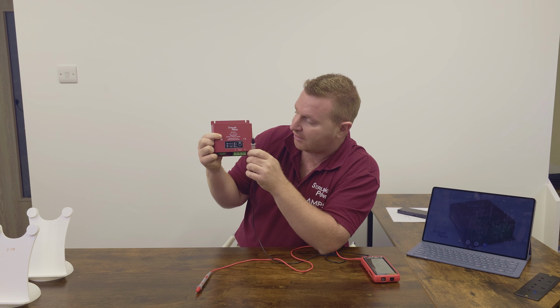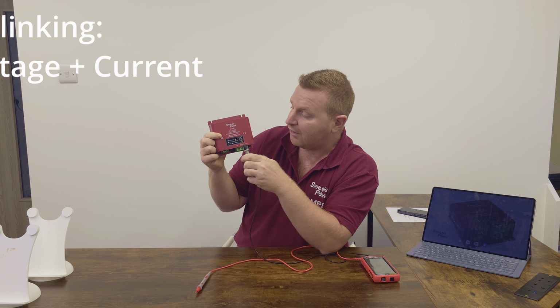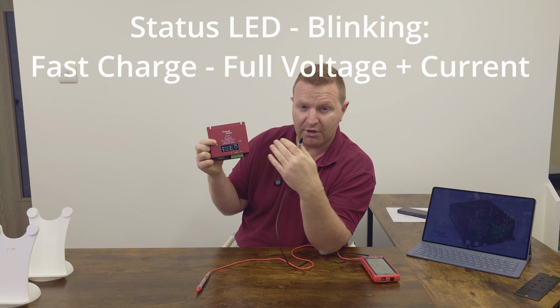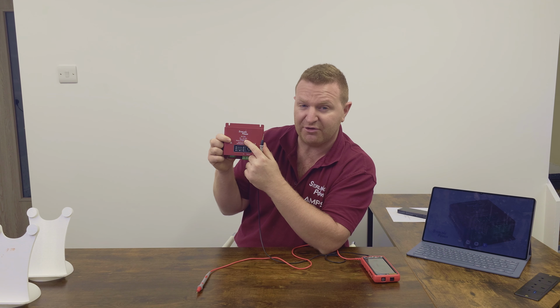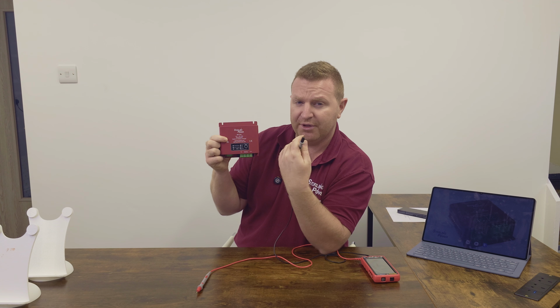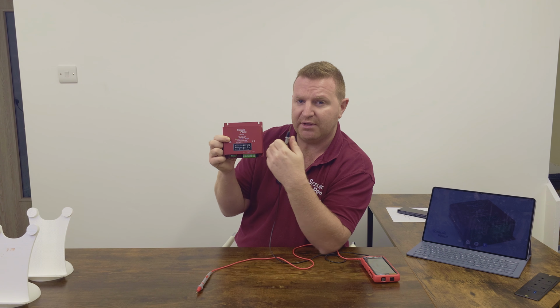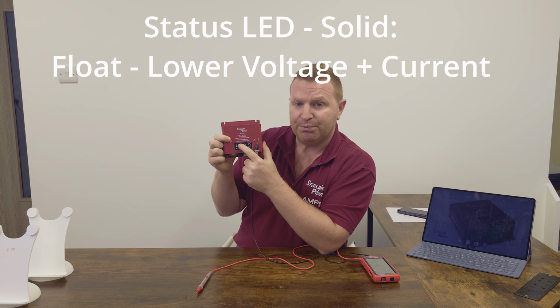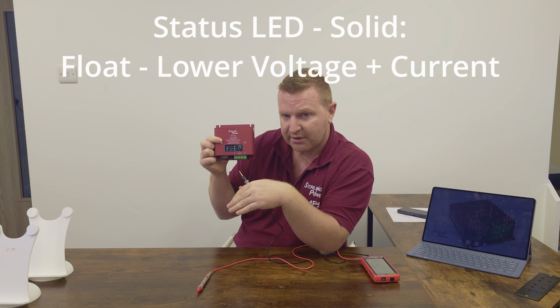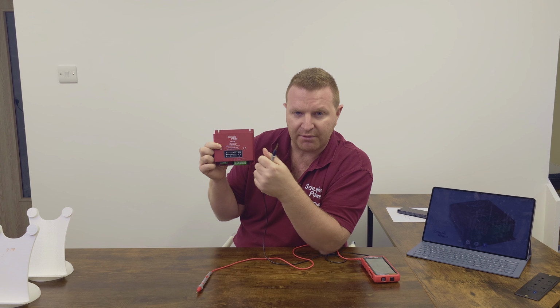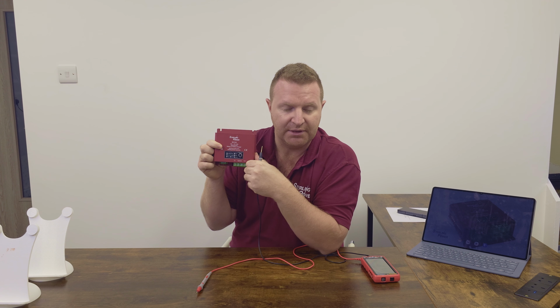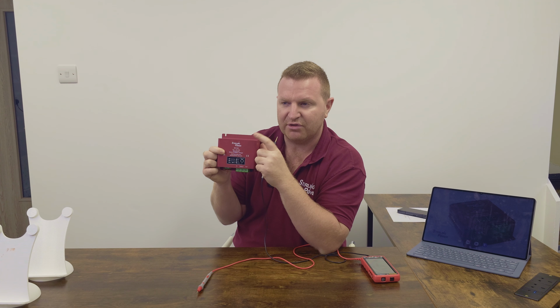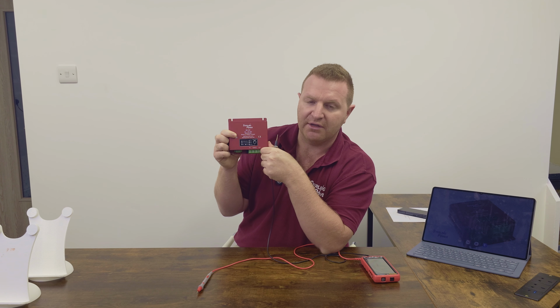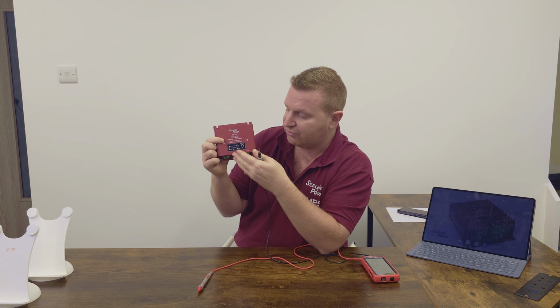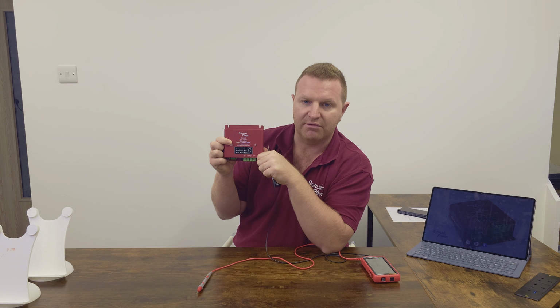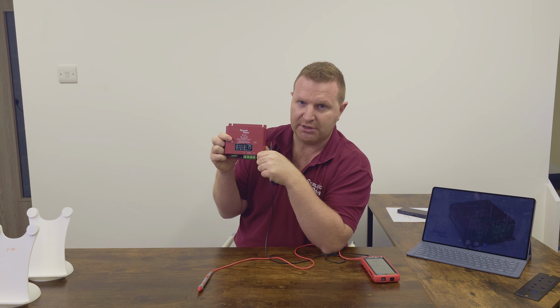Once you hit float voltage, the charging status LED will be on solid. If it's blinking, it's in fast charge, so there should be maximum current coming out of the DC-DC charger—about 24 to 25 amps on the output in this case, or approximately the rating of the B2B on other models. If it goes solid, it's in float, meaning the output voltage has drooped a little, and the current will probably drop to 1 or 2 amps, possibly lower, depending on any load on the output battery. Essentially, by that stage the DC-DC charger assumes your battery is full. It might not be—could be a settings or cable issue—but the B2B at least thinks your leisure or output battery is fully charged.